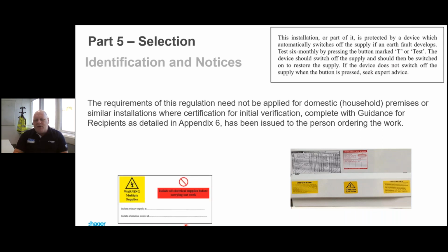Where we have a solar generator on the roof, we have to warn somebody that when they turn this board into the off position, there may be a secondary supply into this board. We need to turn off all the supplies into this board. So that's the only sticker we need to put on, but it is only when we've got a second form of generation into that board.